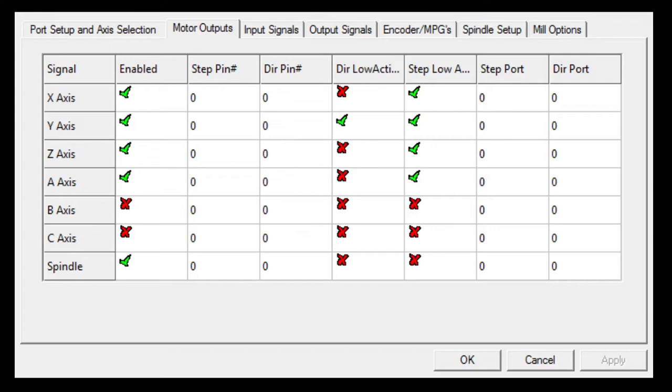The direction low active or high active, if you have an axis on your machine and it is traveling in the incorrect direction, you could simply change the status of this and it would make the axis turn in the opposite direction, or you could physically change the wiring.